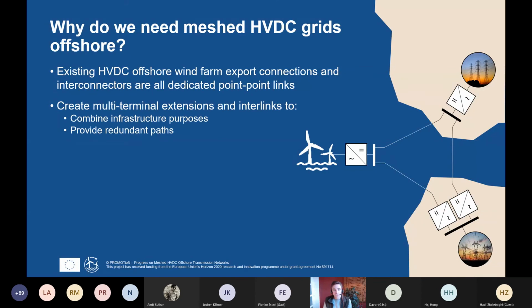Now, both of these drawbacks can be mitigated by providing an additional link between the point-to-point connections, forming what we call a radial multi-terminal HVDC system. The extra link can act as a redundant path in case of an outage of one of the export links, and it can combine functions such as offshore wind export and interconnection of countries using the same infrastructure.